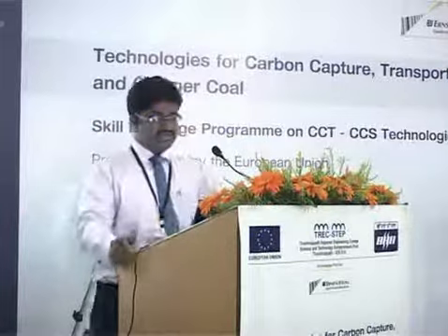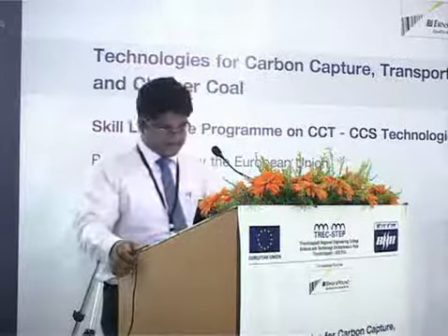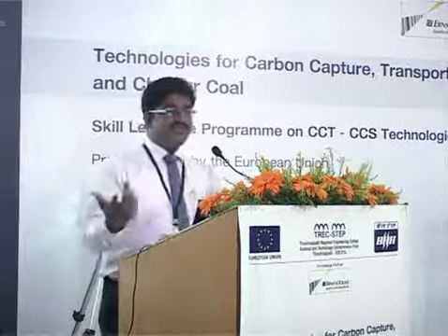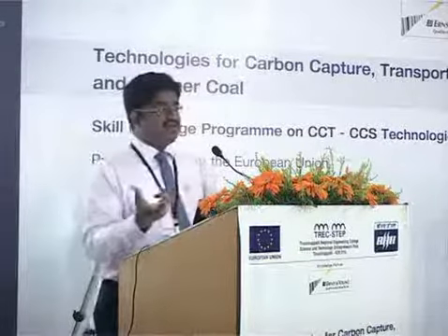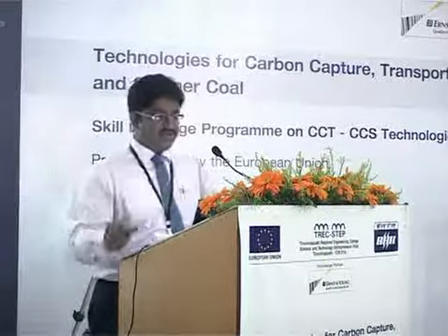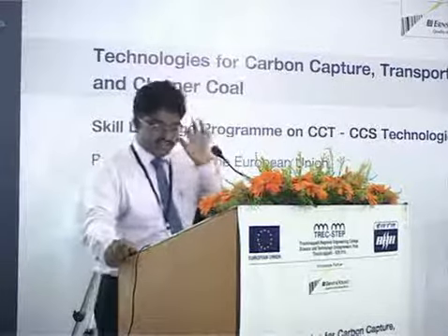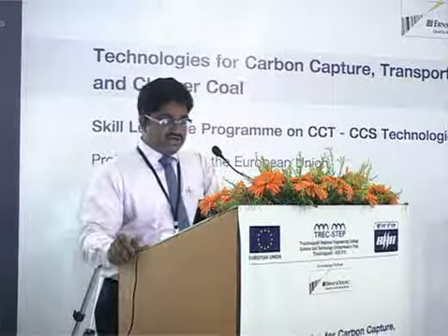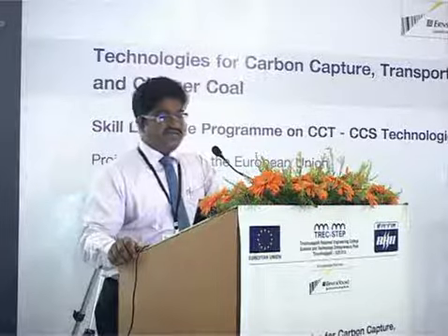Just in a nutshell, they have mentioned their coal consumption rate and their calorific value in terms of megajoule per ton. You would be surprised why megajoule per ton, because the methodology asks for it. Normally we check kcal per kg, so it depends upon the methodology. And if you see their net heat rate before retrofit is about 855.6, whereas after retrofit it's reduced to 821.